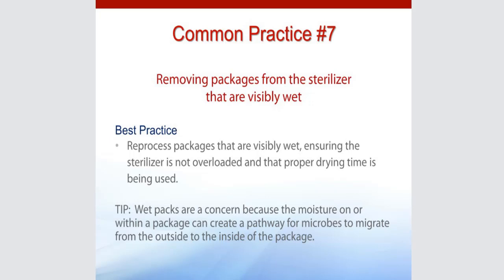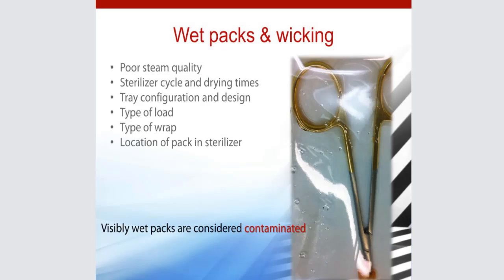So these packs, if they are in fact wet, are considered to be contaminated, which means they either need to stay inside the sterilizer until they're completely dry, or they need to be repackaged and redone. So you need to make sure, if you have consistent issues with wet packs, you've got to look into what's causing it. The number one thing that we see that's causing wet packs is overloading the sterilizer. You're putting far too much weight or mass of instruments in the sterilizer, or it's not being loaded correctly, and the steam and the dry air can't circulate appropriately.